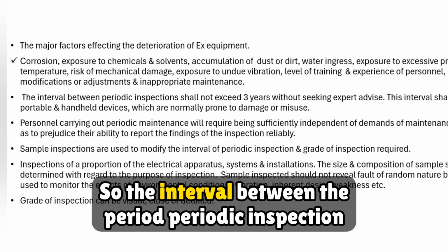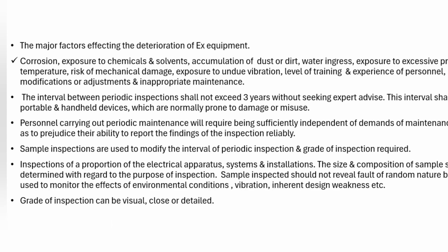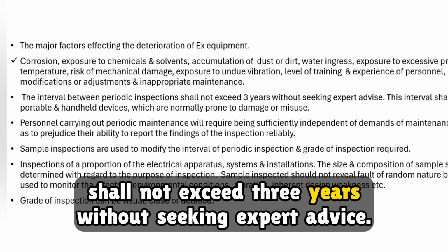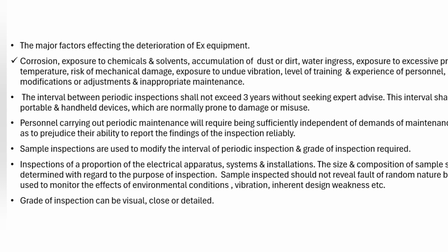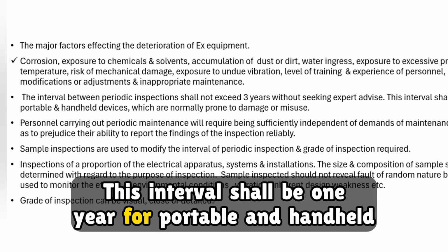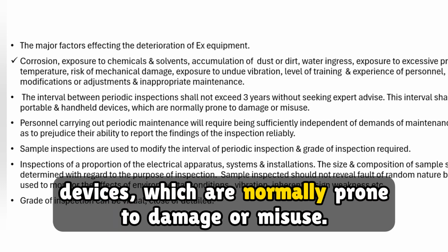So the interval between the periodic inspection shall not exceed 3 years without seeking expert advice. This interval shall be 1 year for portable and handheld devices, which are normally prone to damage or misuse.